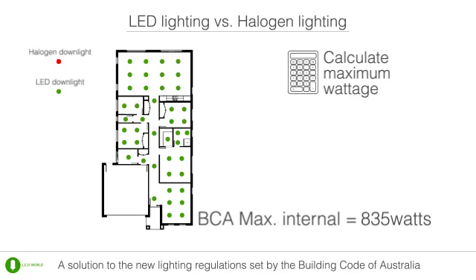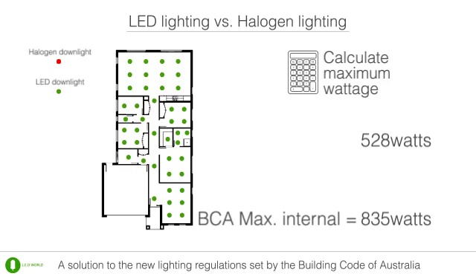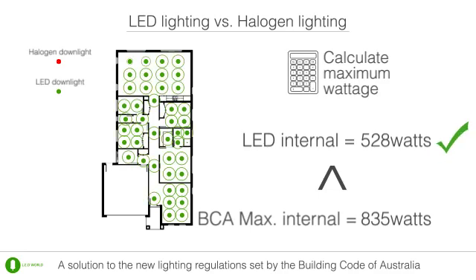To ensure the new LED lighting arrangement complies with the new BCA regulations, simply use the technique previously discussed. The example house has 44 LED downlights, and each LED globe uses 12 watts. A total of 528 watts is being used by the LED downlights to light the internal area of the house. Since 528 watts is less than the maximum of 835 watts, the new LED downlights meet the new BCA regulations.